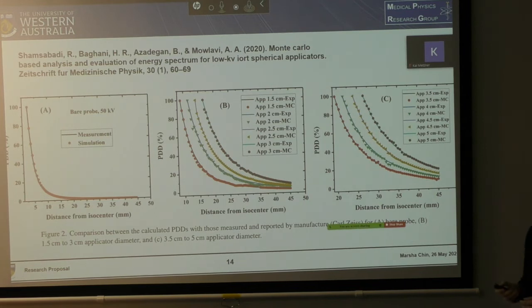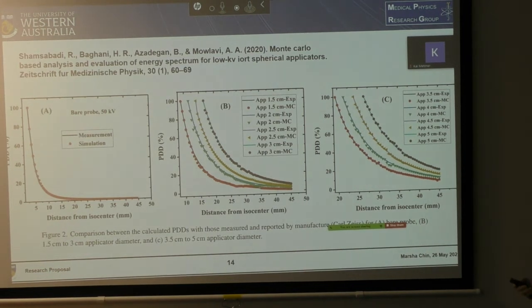So this here is a summary of their results. This is just the bare probe, while these are the various applicators. The solid line is the measurement by the manufacturer, and the dots are from the Monte Carlo simulation. So as you can see, there is fairly good agreement for all the applicators and the bare probe. The uncertainty for their Monte Carlo simulation was about 1%.